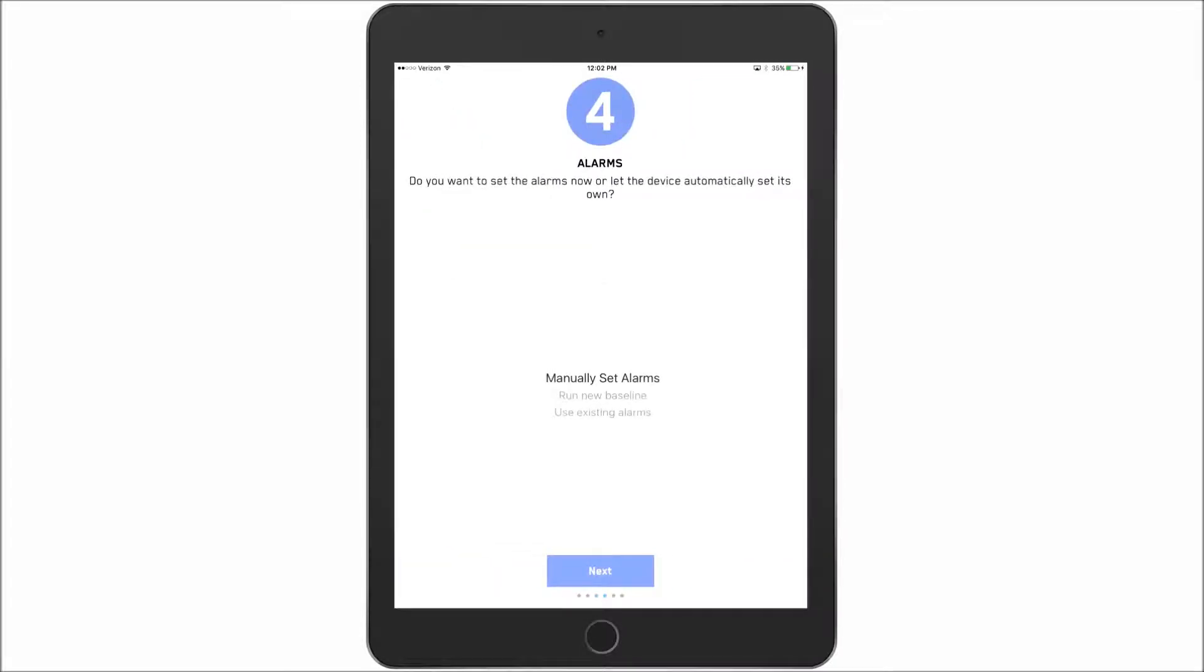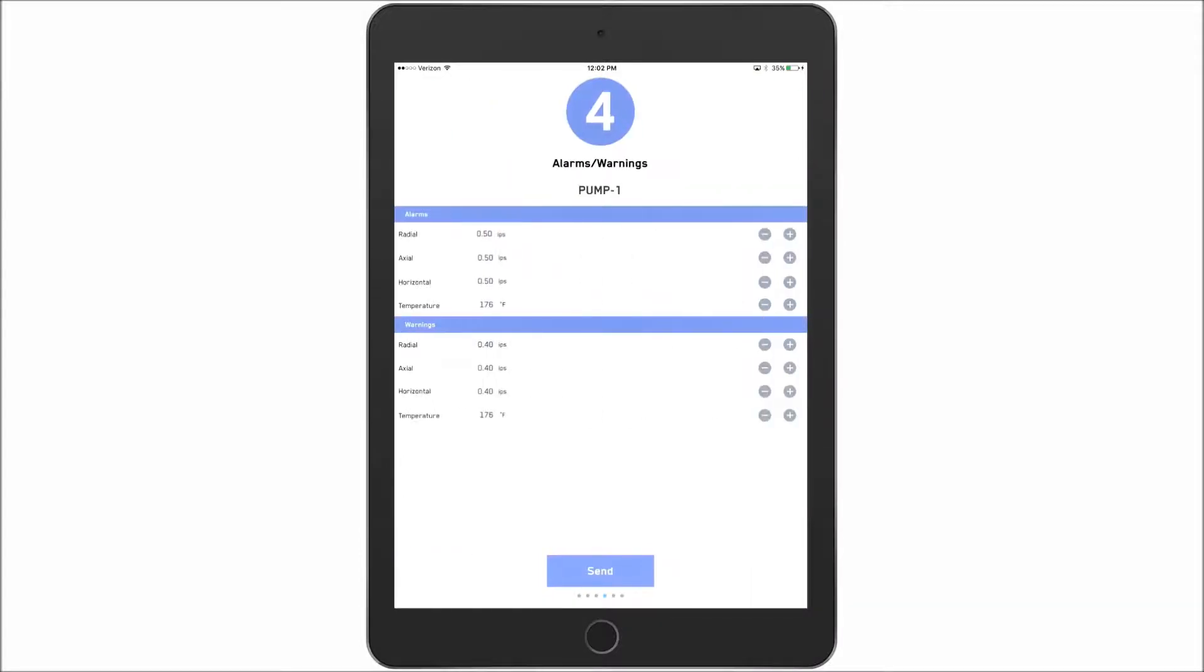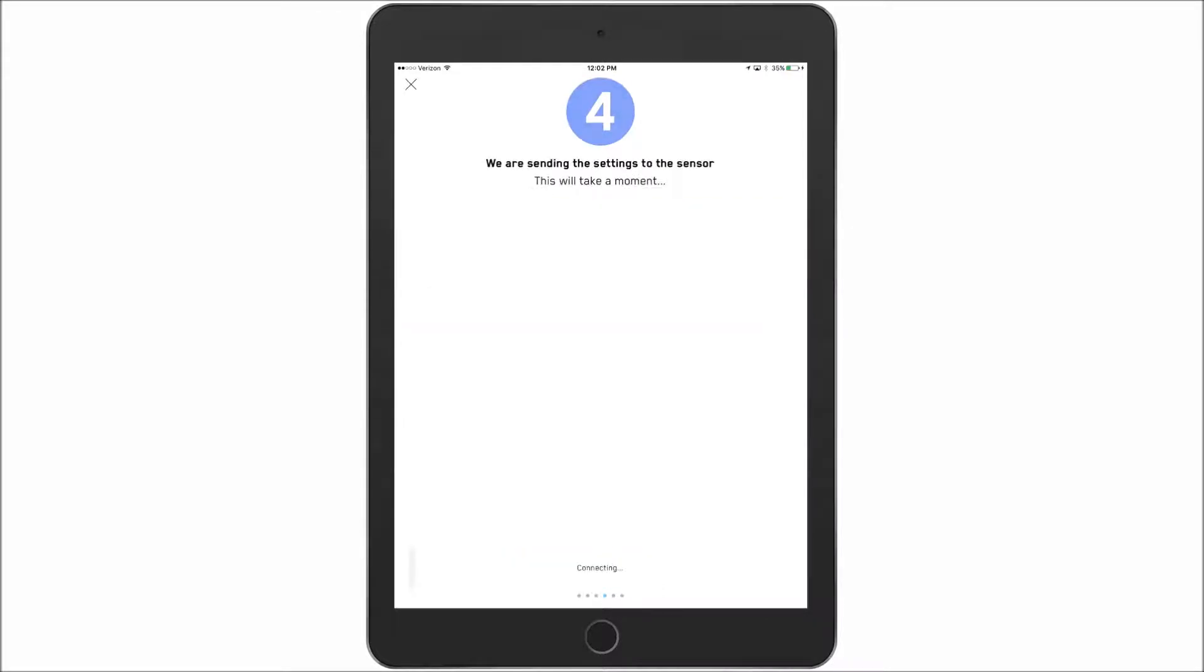And then it'll ask me how do I want to set the alarms? Do I want to do them manually? Do I want to run a new baseline which will take 25 run hours to complete? Or use what's already on the device? For this example we'll do manually set. And I can change say the warning down. And then I say send. And the app will now send those first set of parameters to the sensor and save them.